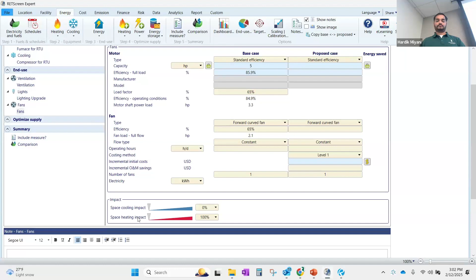Right. Next, the fan and ventilation operate 24/7. That is a constant volume, right? So it is operating 24 hours and it is a constant flow, right? So this is my baseline energy consumption for the model, for the supply fan motor, right? And this is for the heating and cooling being done by the rooftop unit, two separate things, right?